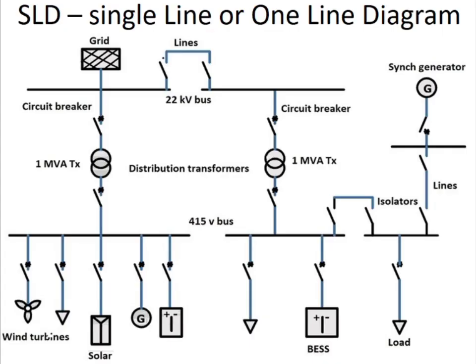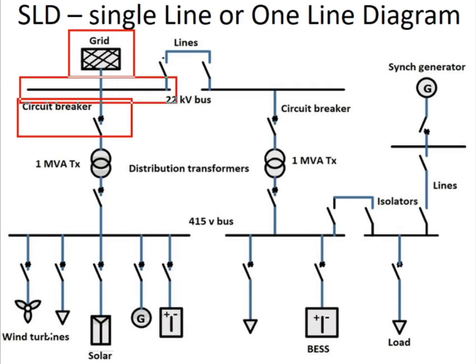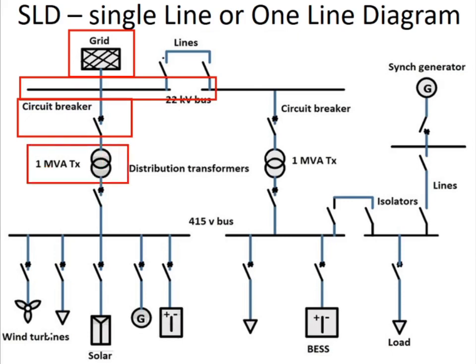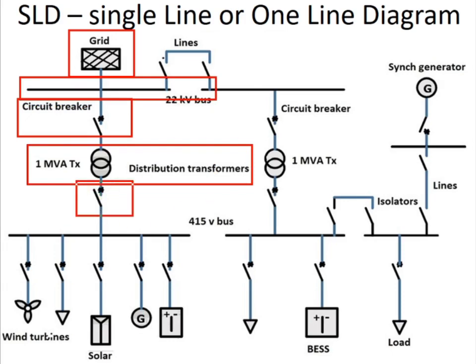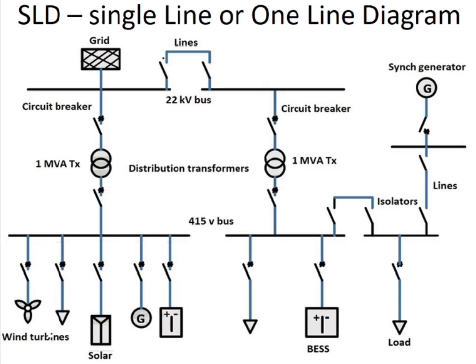Here is another example of a single line or one line diagram. One box represents the entire grid, followed by a circuit breaker and a common bus — a 22 kV bus. Then we have a 1 MVA distribution transformer, an output breaker, and a 415-volt low voltage bus.